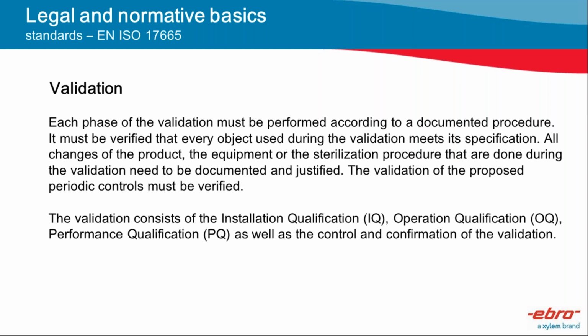Okay, so process validation is therefore the analysis of data. The analysis of data gathered throughout your procedures, throughout all those procedures that we have talked about. So accuracy, therefore, of the products is very critical to making these validation procedures successful. Please bear that in mind. So it's not just using a simple thermocouple or a simple temperature thermometer, because all this data must be analyzed thoroughly and according to the design and also the manufacturing of a product that you produce, and confirm that the process can reliably output products of a determined standard. So that's actually what validation is all about.